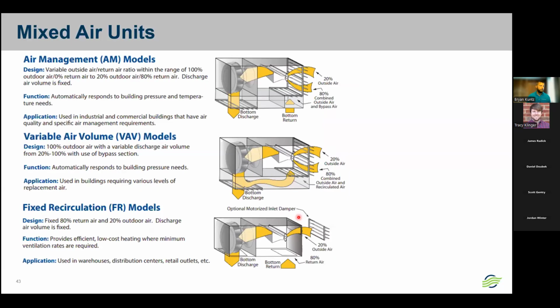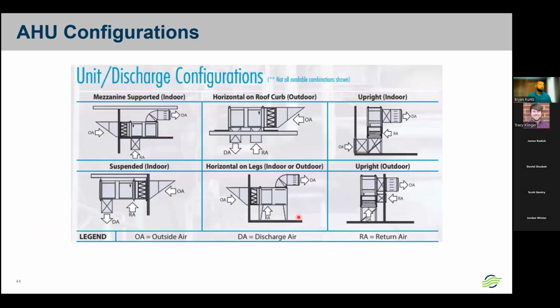So you heard Jamie mention a few times on air management. Those are also called 80/20 units: 20% outdoor air, 80% return air. You can also see the variable air volume models, fixed recirc models, and of course the 100% outside air model. Those are the four groupings that we operate with. As far as configurations go, it's pretty much anything and everything. We're pretty adaptable, given a unique situation.